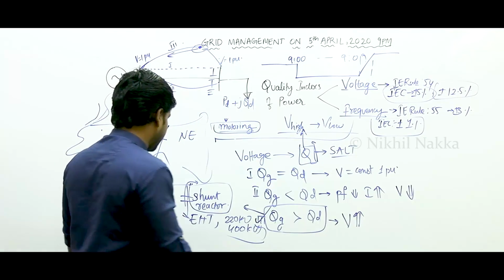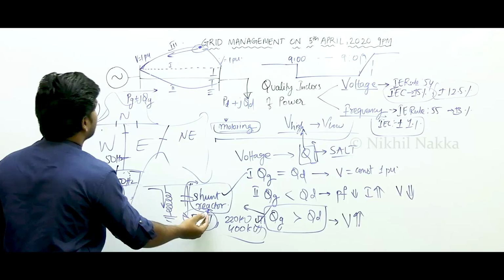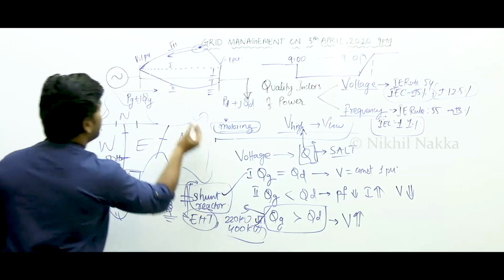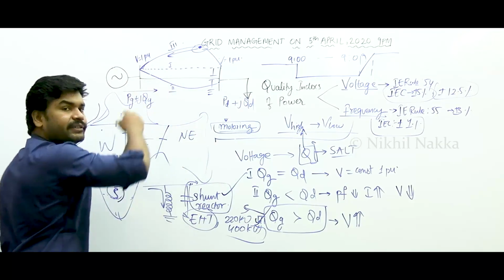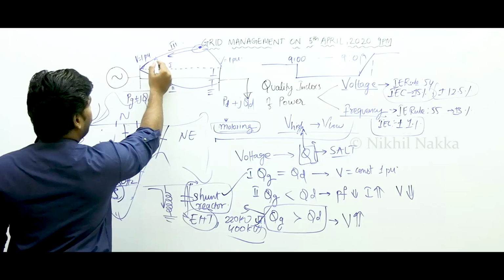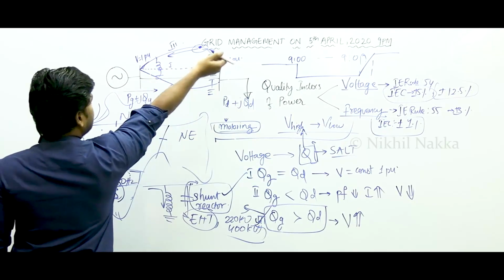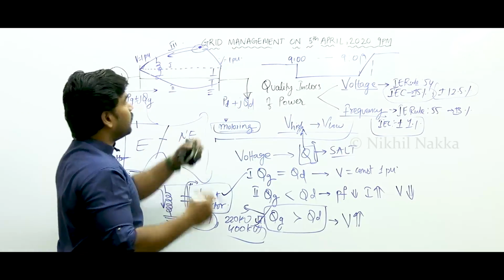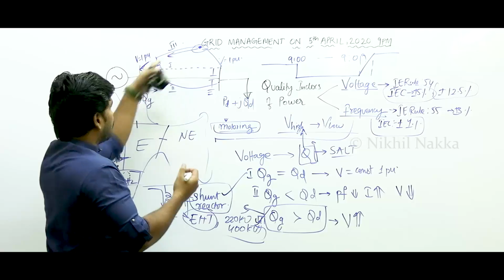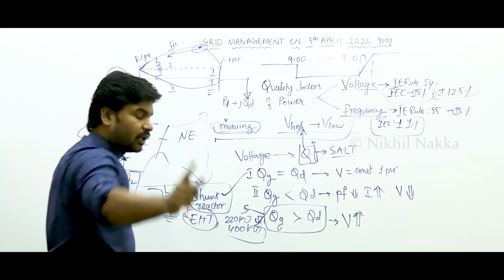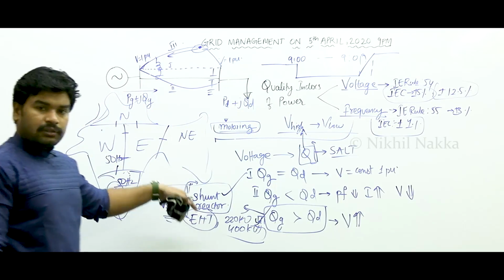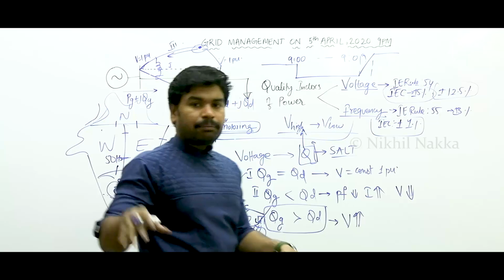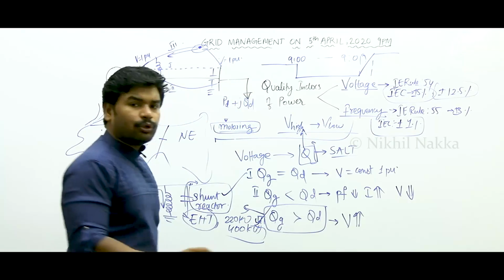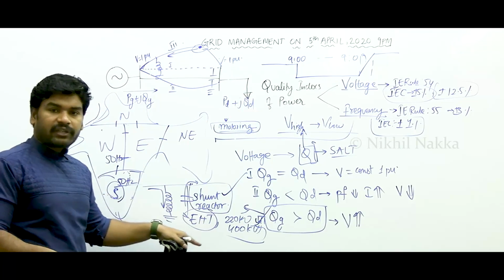Now I am telling that shunt reactors are placed where? EHT substations, 220 400 kV, means this region of the transmission line, isn't it? So this is where we are placing the reactors, because the incoming power is from there, reactive power is from there, to consume that. Understood? I hope you're getting the point. So in order to save the entire power system and to bring back the voltage profile to normal, we will do this kind of corrective actions.